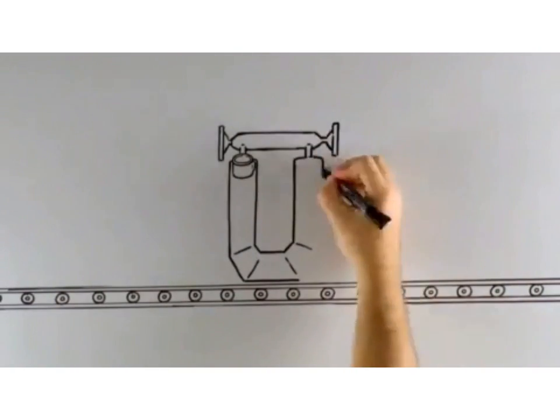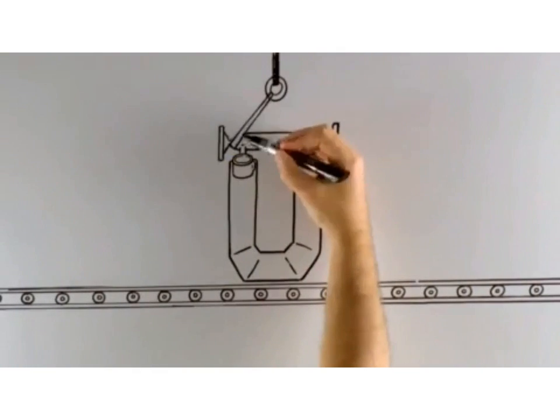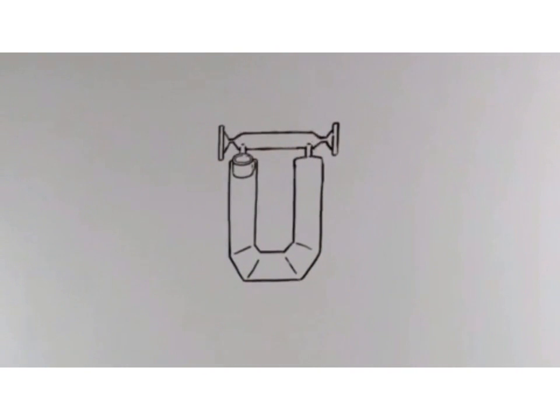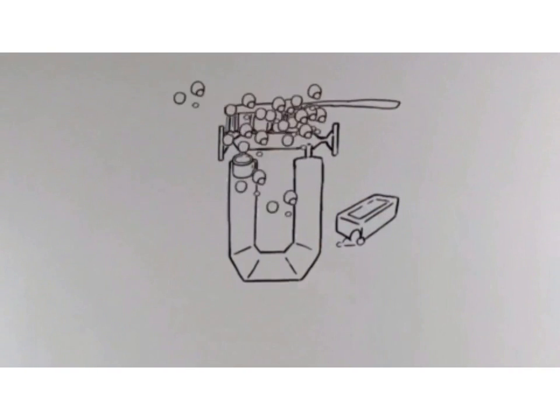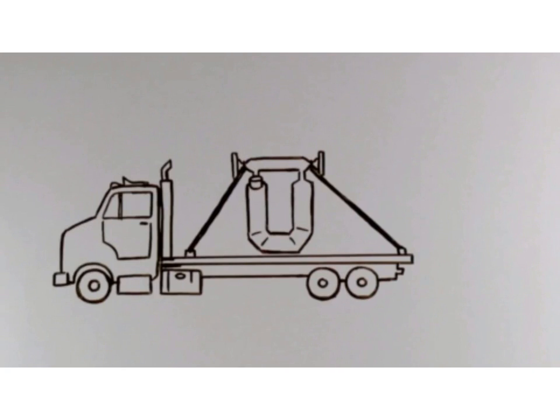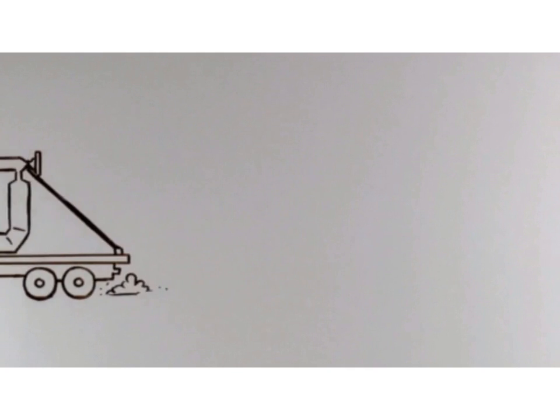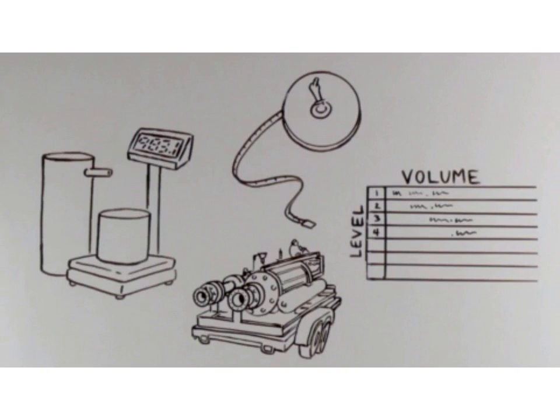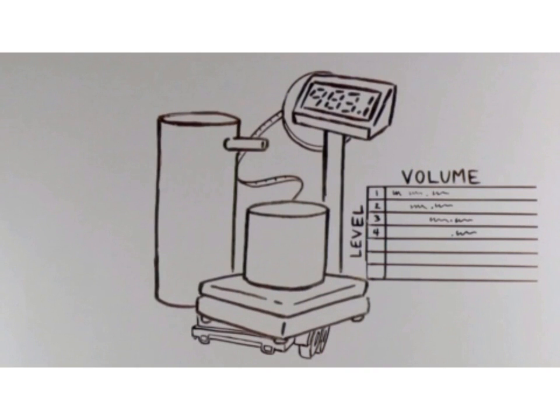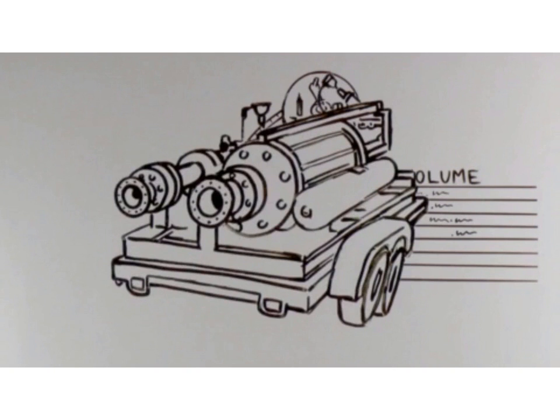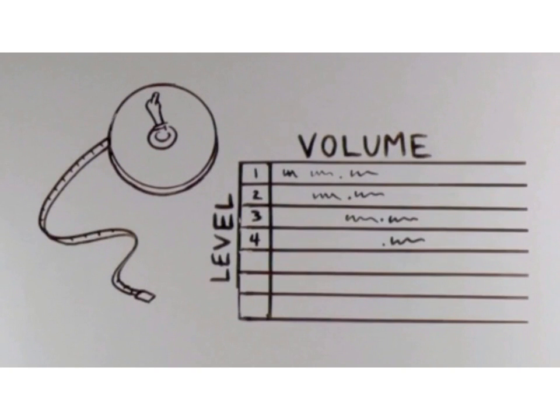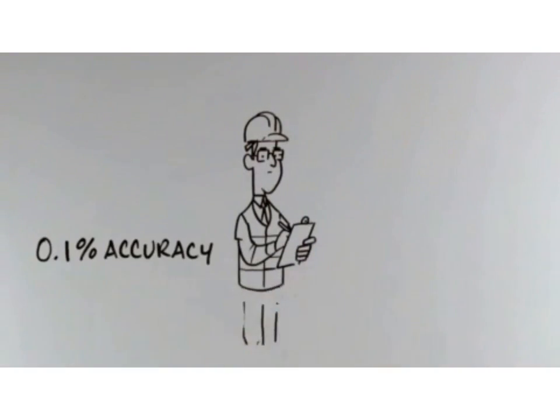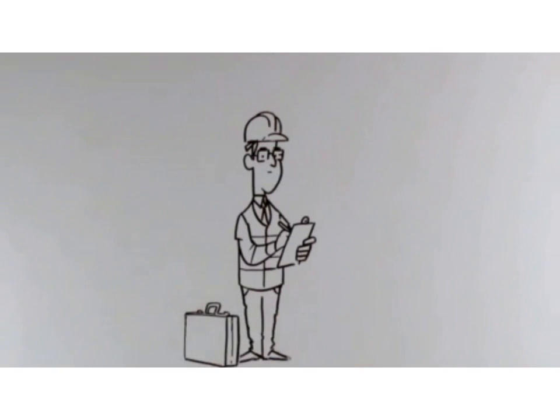His applications call for proving meter accuracy at regular intervals. But pulling meters to be drained, cleaned, and shipped to a lab means Tom has to interrupt his process and reduce production. In addition, removing meters increases the risks of damage during transit, and there's no guarantee the meter's performance will improve. To combat that, there have been pretty inventive ways to verify and calibrate meters on-site or in the lab, like catch and weigh tests done with a bucket on a scale, the use of master meters and portable provers, or even gauging the tank level against an old strapping table. When you're trying to calibrate a meter with 0.1% accuracy, these techniques might not stand up to an audit.